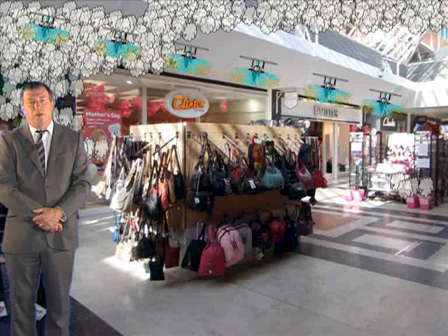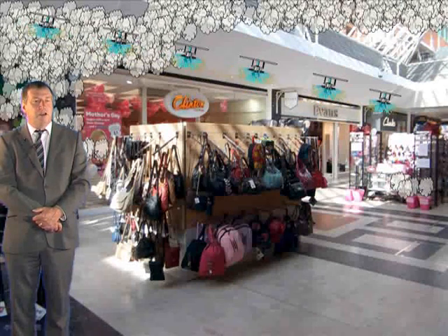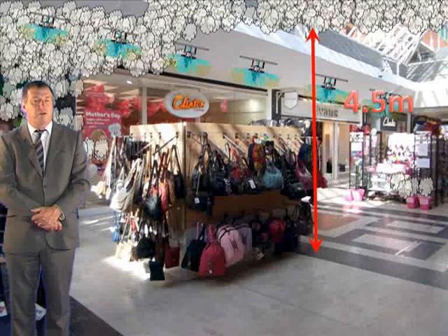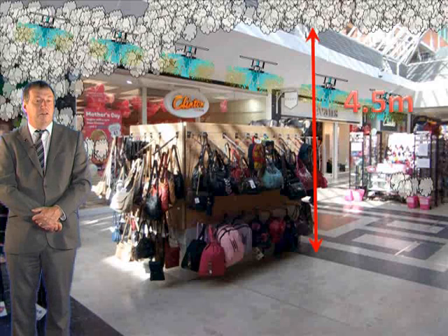Let's look at another example using this spill plume model to determine the mass flow rate of smoke entering the smoke layer. Let's say we've got a shopping mall with quick response sprinklers and a design height for the base of the smoke layer at 4.5 metres above the ground. Let's also assume that the height of rise is less than 2 metres.